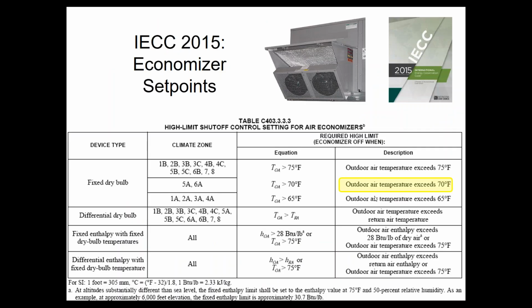Taylor's asking about fault detection and diagnostic on economizers. We will get to that here in a second. Once you do have an economizer, like Climate Zone 5A and 6A, as you can see, require economizers. If I have a dry bulb control, I got to set it for 70 degrees. I can no longer set it for 55 like we used to do 20 years ago when I started working here. I can't even set it for 62, which is my favorite number to set it for. I got to set it for 70 degrees.